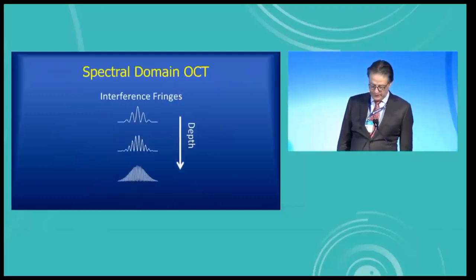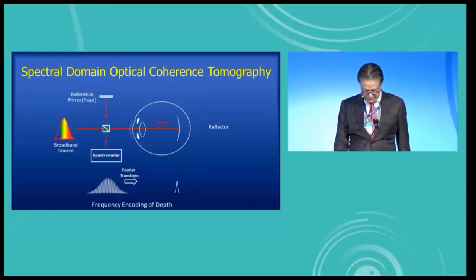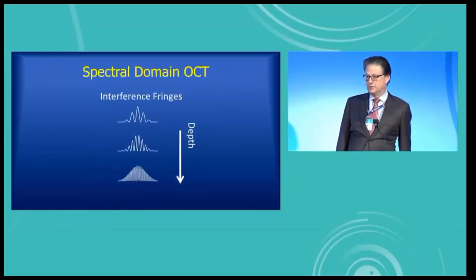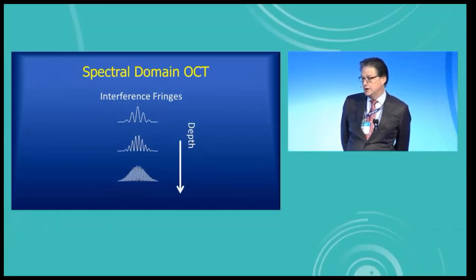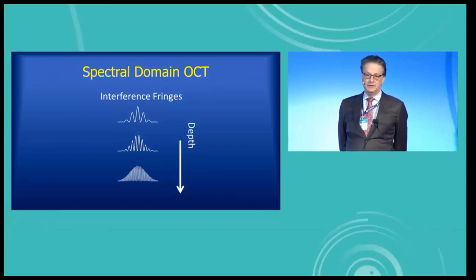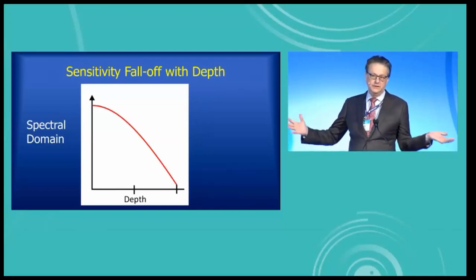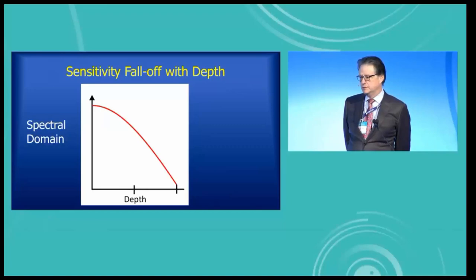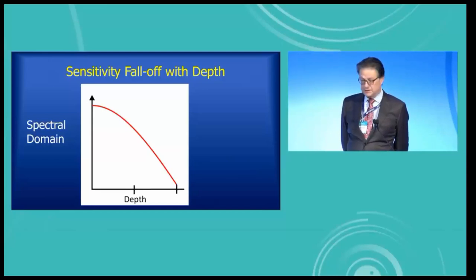You end up getting a fairly complex waveform that can be decoded with a Fourier transform to make an A-scan, and many A-scans make a B-scan. The ingenuity of spectral domain OCT is that there's depth encoding of the reflection, but that's also one weakness in that it's harder — the instrument is less sensitive to these higher frequency interferograms. So increasing depth also means decreasing sensitivity.